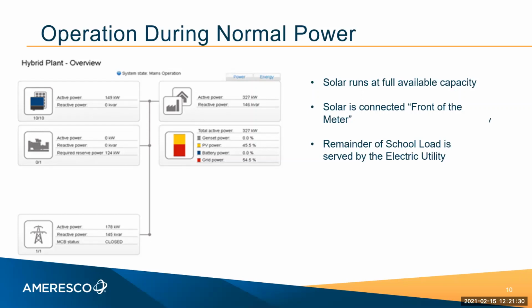The way it runs in normal operation is whatever is available from the solar, so 100% of the solar, is output by the system. If there's additional load required, so in this case, it was 149 kW coming out of the solar array, and there was 327 kW, which is the top right box, being consumed by the facility. So the rest of the power, which is in the bottom left, is the grid, was 178 kW, and that was fed from the grid. And you can see in the bottom right box that of the 327 kW total, about 45% was supplied by the PV, and the other 55% was from the grid.